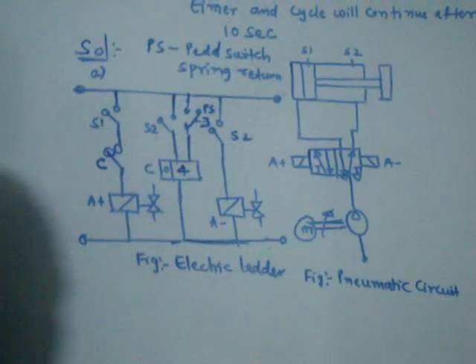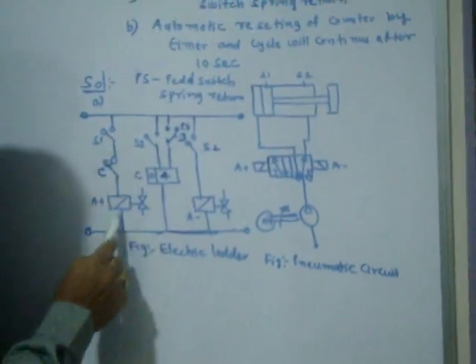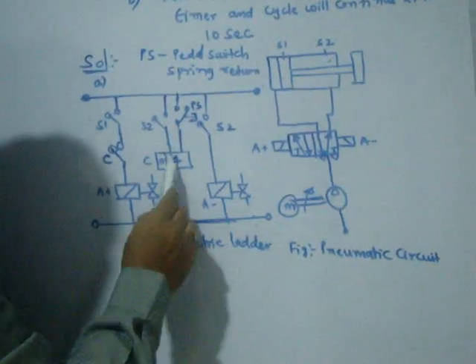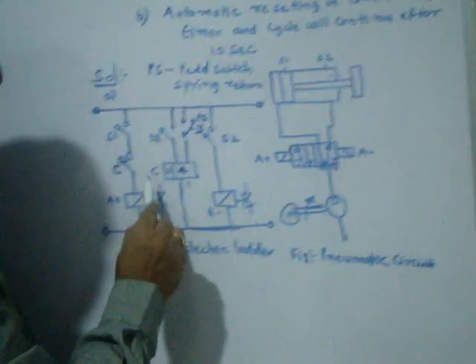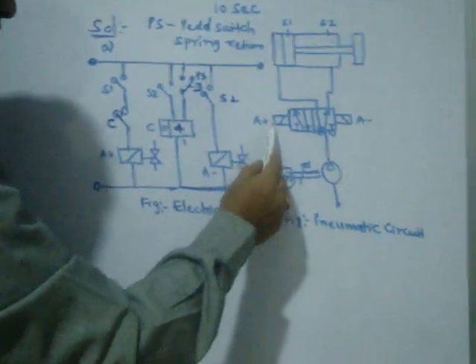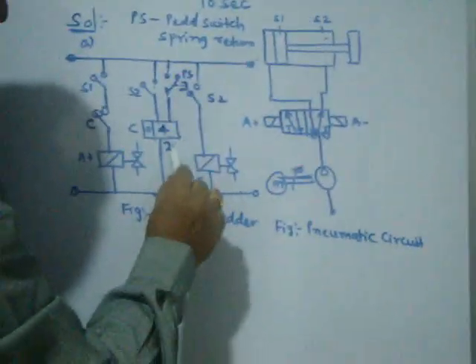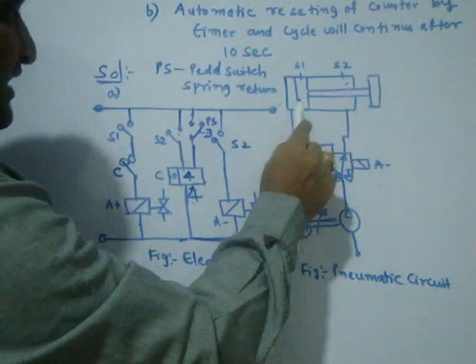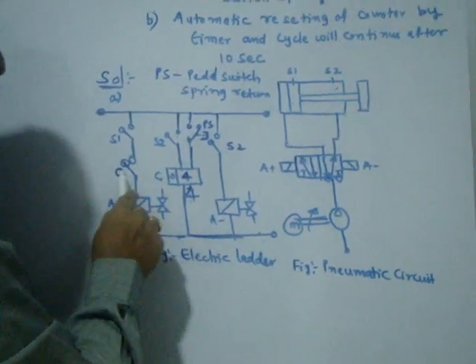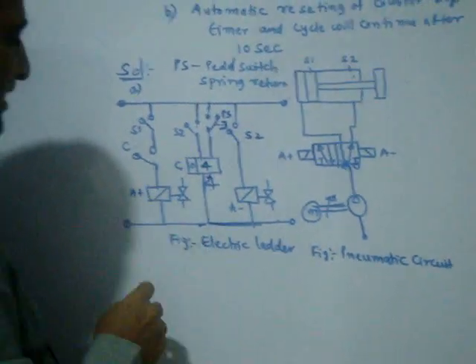I will explain once again how it works. The piston is at S1 — it closes, current flows to A+. When A plus is on, the piston goes to S2. When the piston goes to S2, it closes — the counter counts one. At S2, A minus brings it back. Once again it goes to S2, it counts two; comes back; three; goes to four. When it goes to four and comes back, counter C turns on. Then automatically this normally closed contact opens, breaking current to A plus.